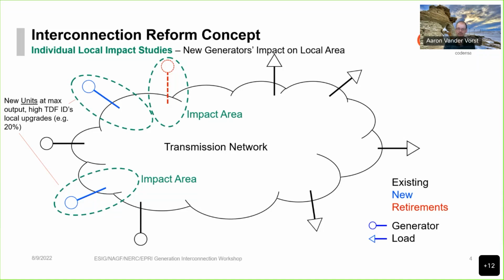The third characteristic of the individual local impact study is using reasonable assumptions about seasons and load profiles under which the generator would most commonly produce energy. This is commonly referred to as a fuel-based dispatch. This approach also ensures that an interconnection request is funding upgrades that are most impactful to its actual generating profile.